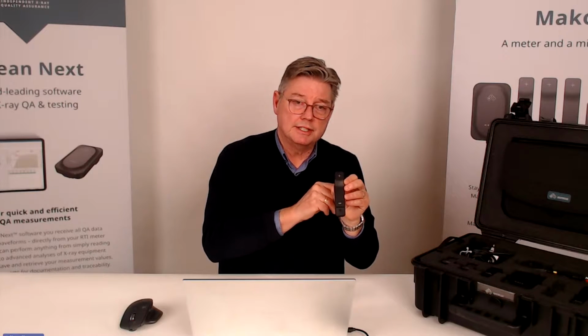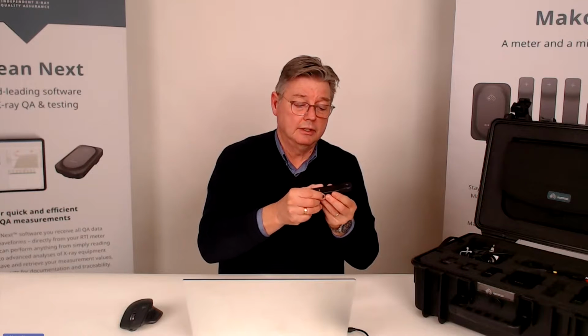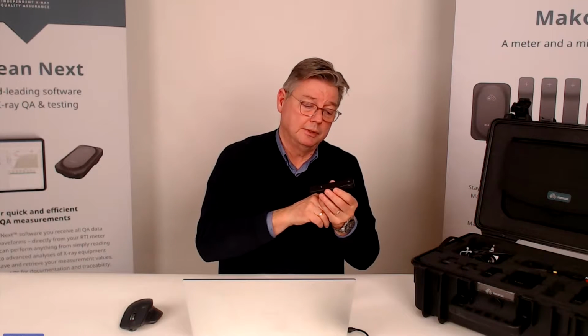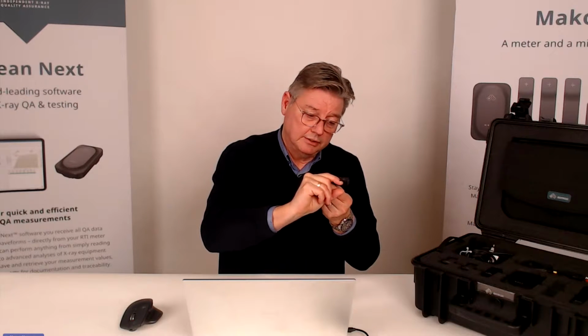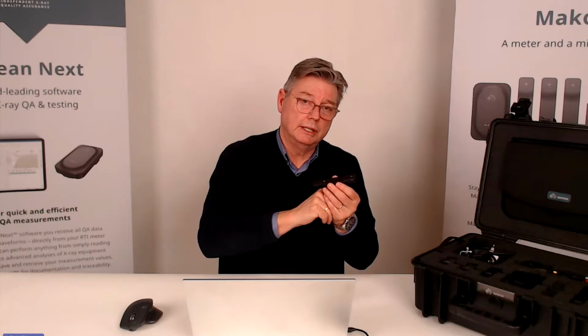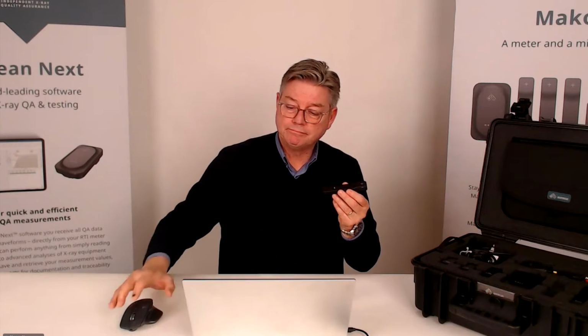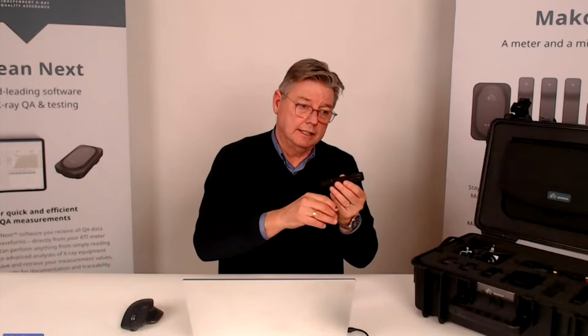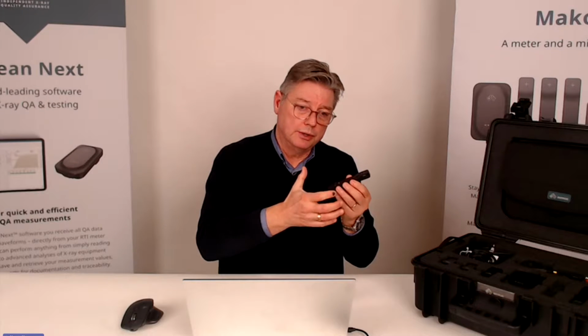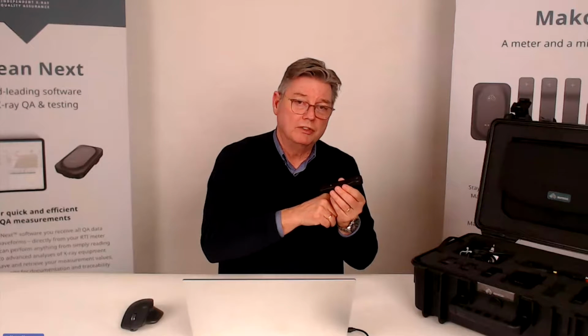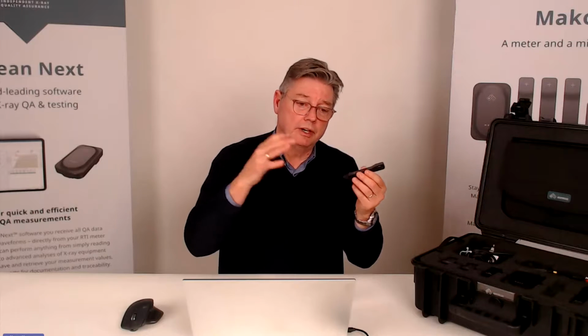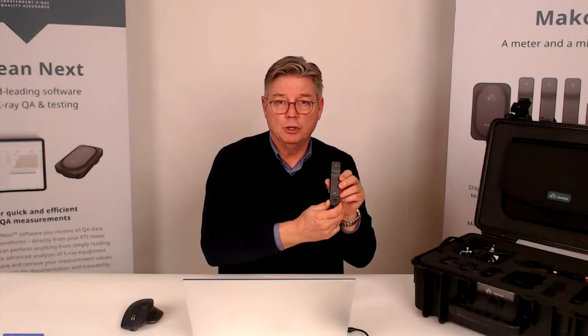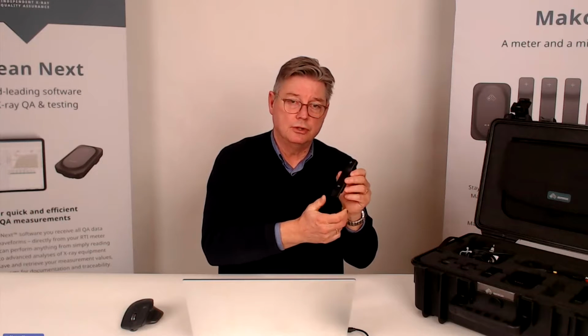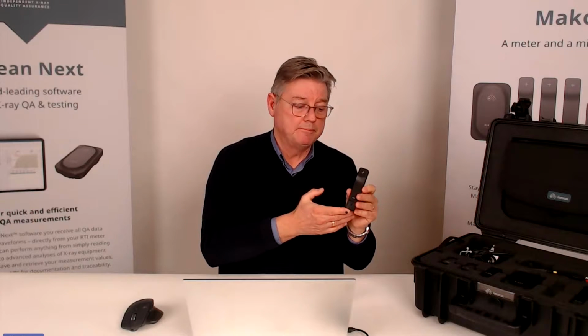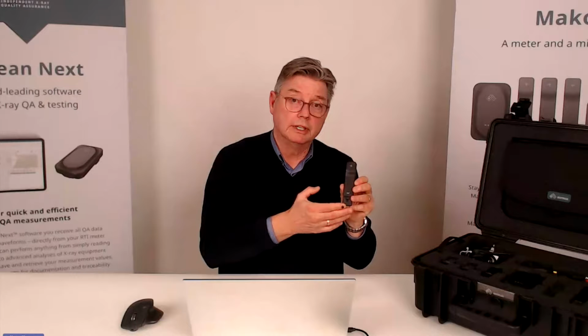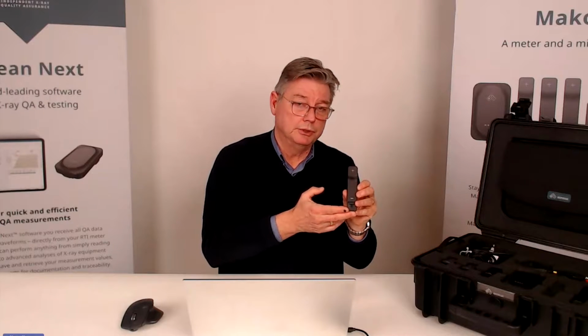So we're talking about the detector design. It's novel. The design is such that it's layered diodes in the detector, so that the detector has multiple layers with dedicated special filters in between. And that then allows for the algorithms to process and work with data and provide highest accuracy and also a very wide dynamic range. For the RF probe, which I'm holding here, the kV range is 35 to 155 kV. So it covers all of the radiographic and fluoroscopy and CT systems on the market today.